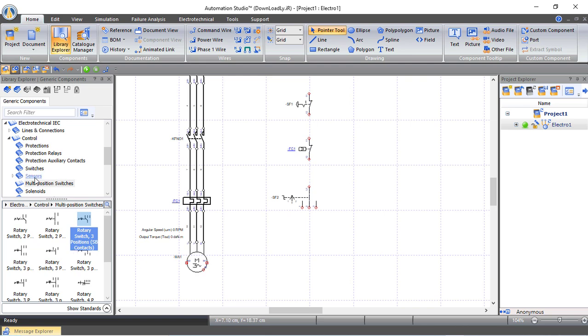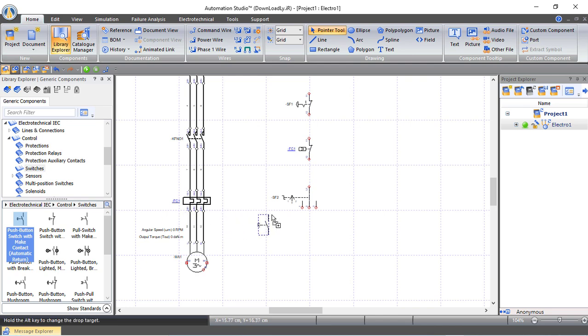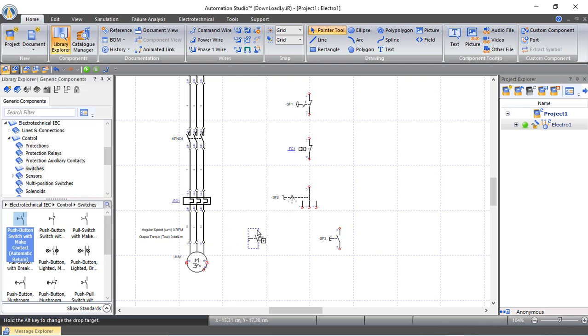From switches we bring two normally open push buttons. Push button 3 is used for jogging operation — press it and the motor starts, release it and the motor stops. This is the same principle used in electrical overhead cranes: hold the button and the crane moves, release it and the crane stops immediately for safety. Push button 4 is used for continuous operation.